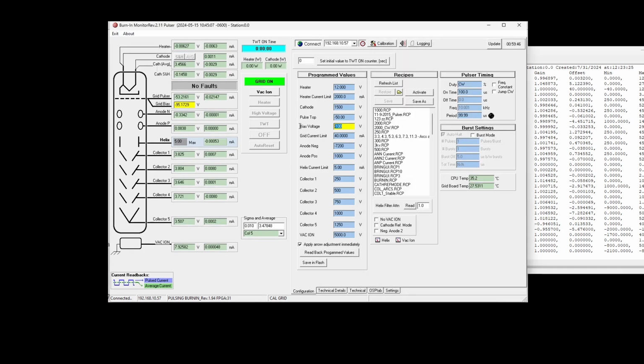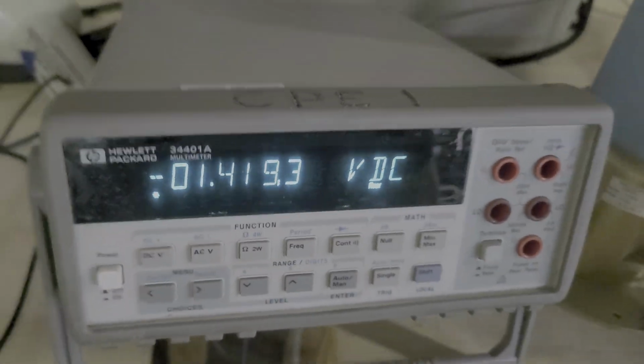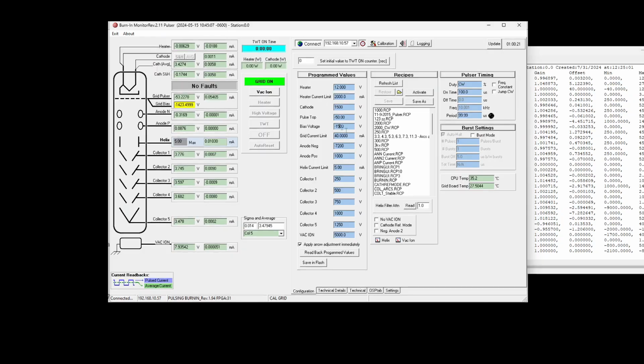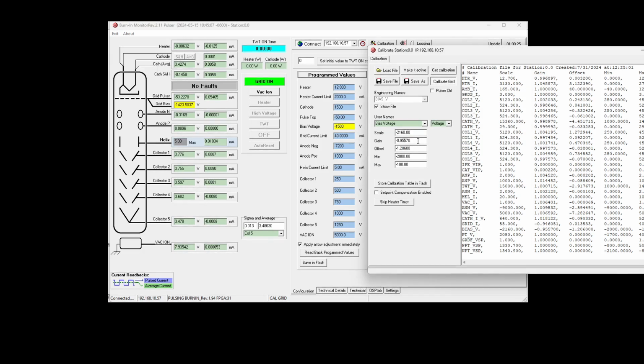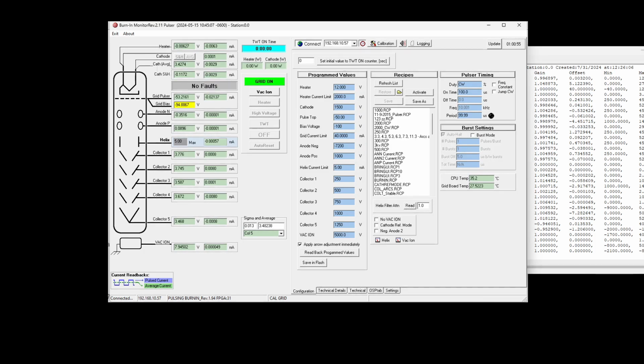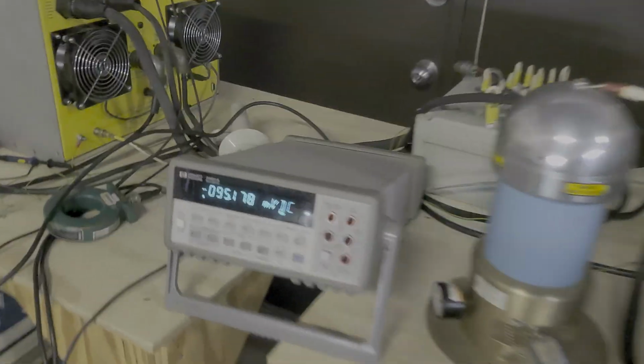1.206. Okay. Let's take this back to 1500. Double check that this is still at 1419.0. It's 1419.3. Let's recalibrate gain to that. 1419.3 using our gain. There's 0.3. 1419.3. Let's also drop back down to 100. This will be the last time. I usually can get it pretty close within 3 iterations. It's still at 95.17.